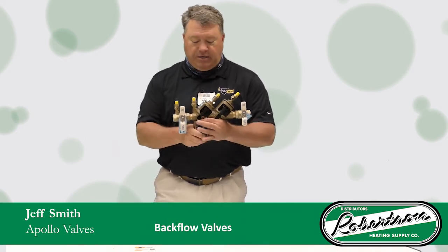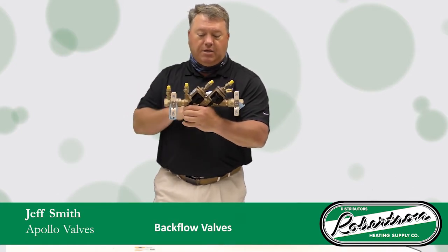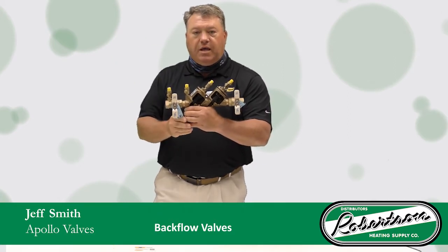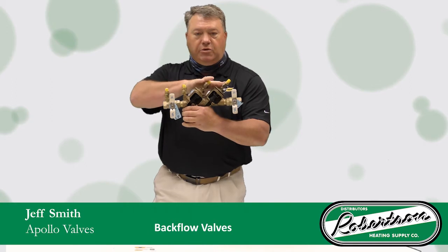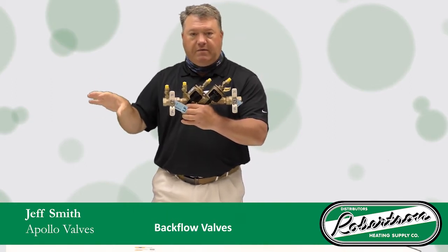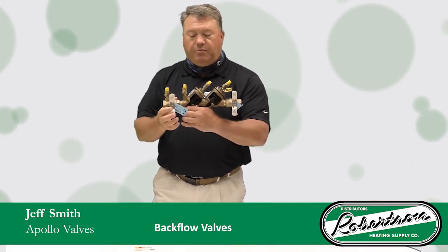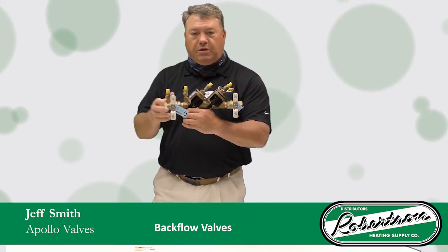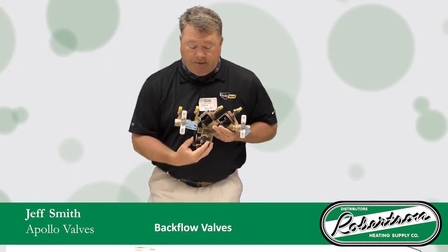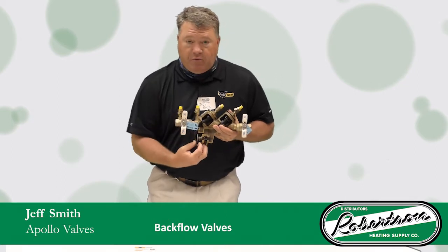The double check basically is what we have here. If I cover up this relief port at the bottom, it's two checks in place that will lift up as the water comes through, and whenever there's a back siphonage at the water main or on the inlet side, these two checks will shut, protecting the main drinking system, but not so much the building. So they figured we need to protect the building and the occupants in the building as well as the main system, so they came up with the RPZ. And with the RPZ, we add this relief port on the bottom. So whenever that same situation happens, the water will come back, and now we will dump it down the drain.